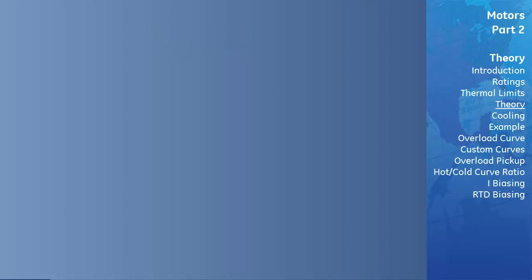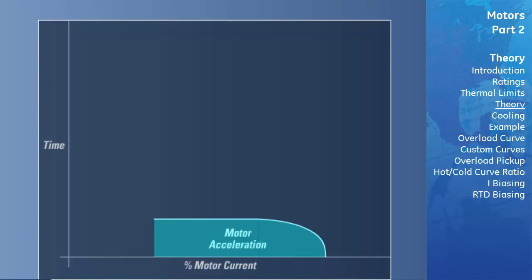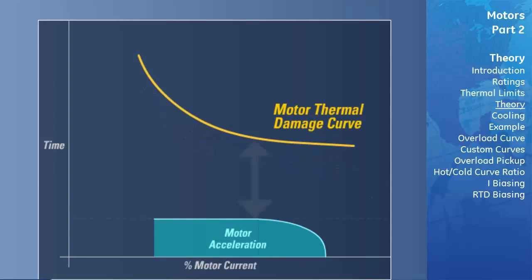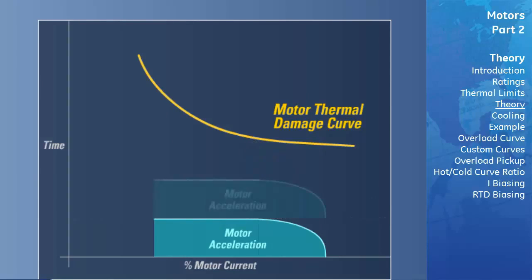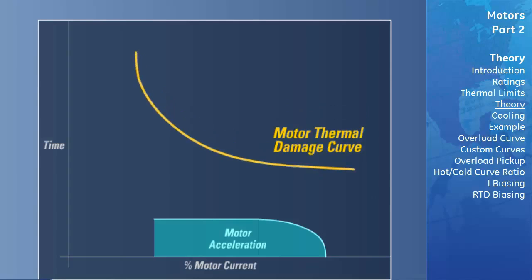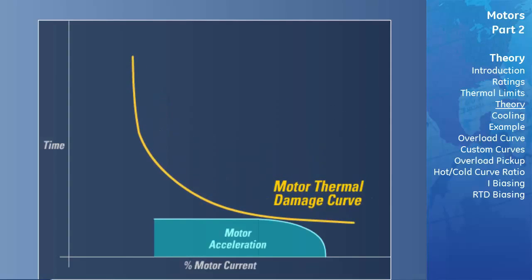This all sounds very complex, but it is actually quite easy to understand. If the motor has been designed fairly conservatively — that is, the portion of the acceleration curve under the motor thermal limits curve is less than a third to a half in terms of trip time, and the motor has been applied conservatively such that the acceleration and thermal limits curves do not cross — then thermal model settings can be set fairly easily. If the acceleration curves and thermal overload curves are very close, accuracy in the settings becomes very important to ensure reliable motor protection without nuisance tripping.